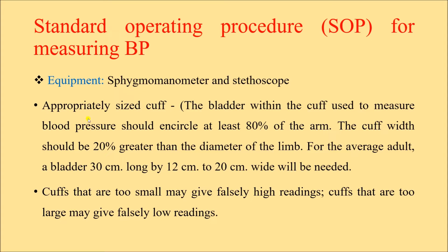If the cuff size is too small or too big for the subject, it can give false readings. The bladder within the cuff should encircle at least 80% of the arm. The cuff width should be 20% greater than the diameter of the limb. For the average adult, a bladder of 30 cm long and 12 to 20 cm wide is needed. If the cuff is too small it gives falsely high readings; if too large, falsely low readings.